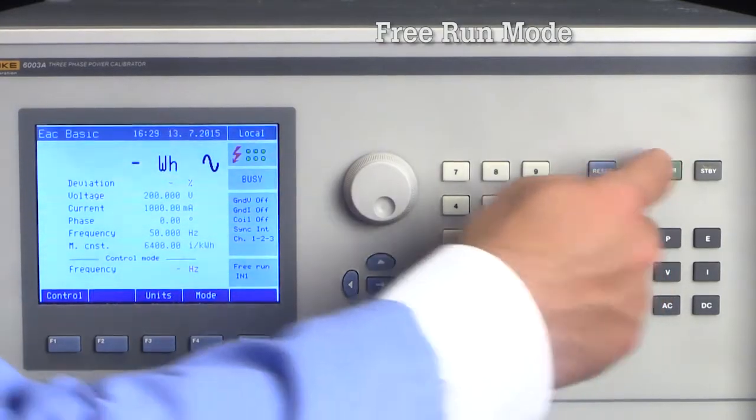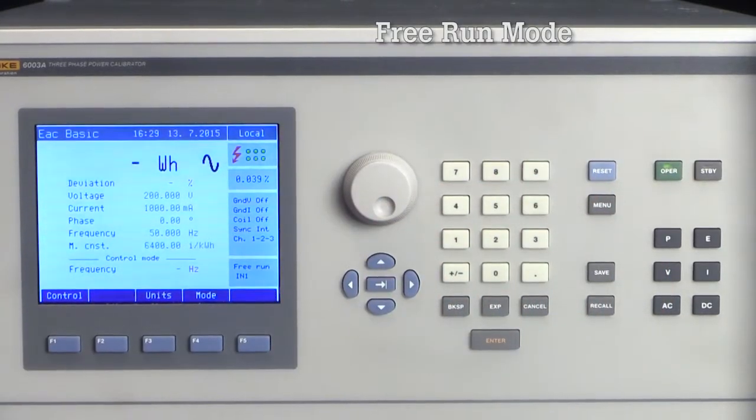I need to set the meter constant or frequency to match the meter's pulse output, which for this meter is 6400 pulses per kilowatt hour. To start the test, I will push operate and the test starts. The 6003A outputs 200 volts, 1 amp into the UUT. In other words, it delivers 200 watts to the meter. The 6003A receives the pulses back from the meter and, based on the meter constant, expects an exact frequency of the pulses.